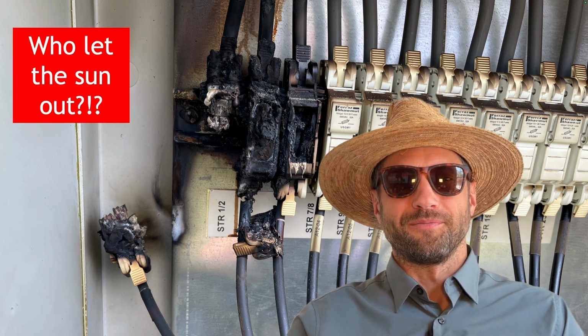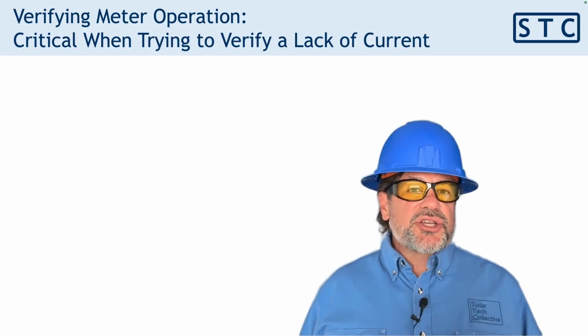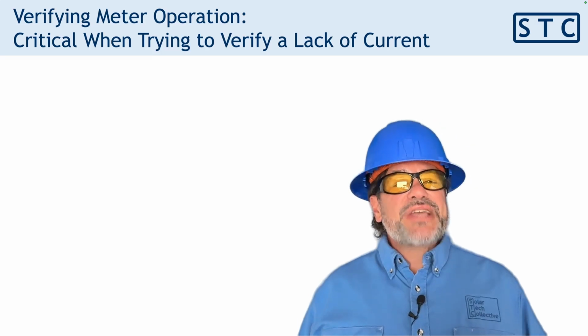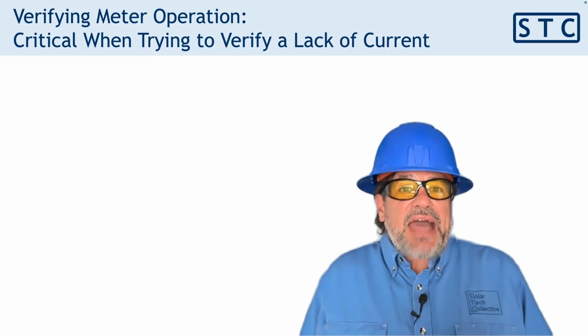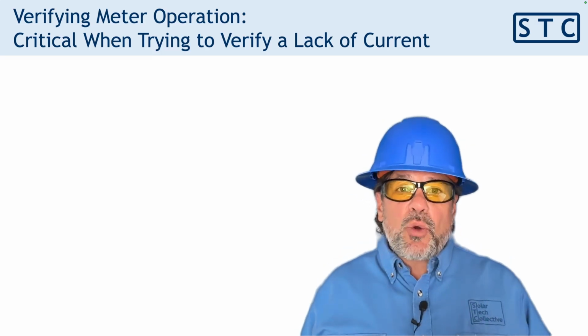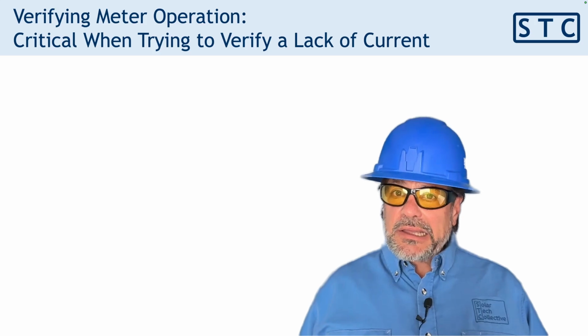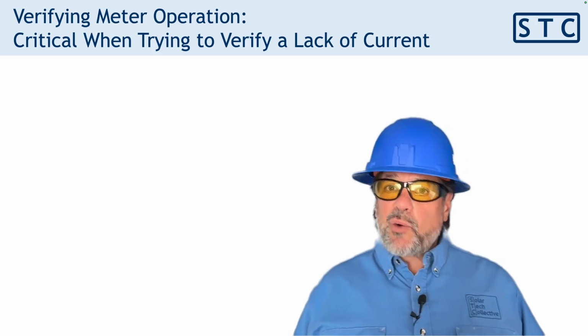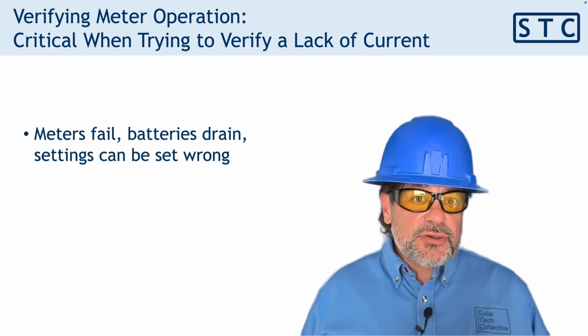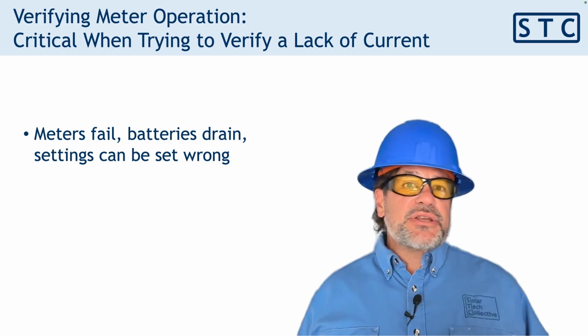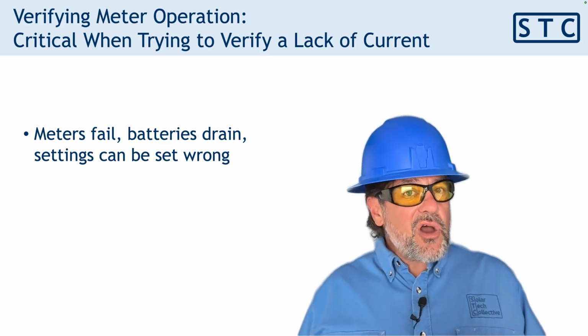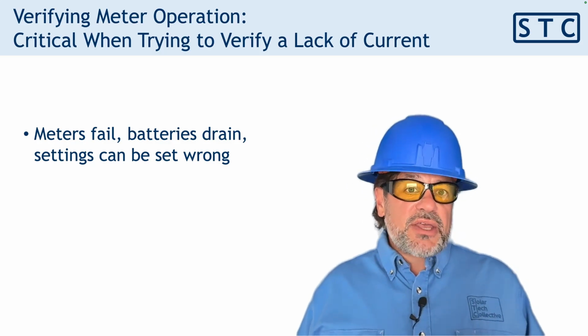Well, verifying correct meter operation is absolutely critical when we're testing a circuit to make sure it doesn't have any current on it. There's a lot of ways to get a false zero reading that can make you think things are okay when they're not, and that can lead to hazards. Meters fail, batteries drain, meters are set wrong. All of these can give you that false zero reading.